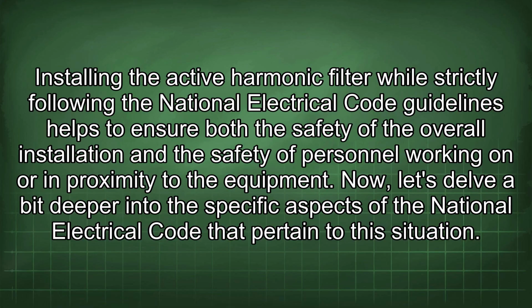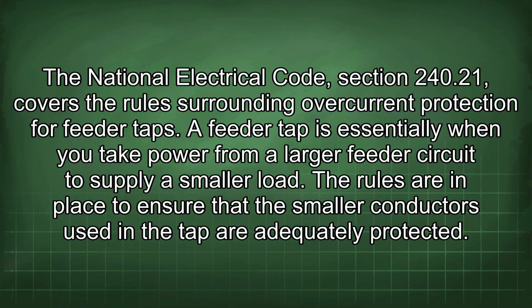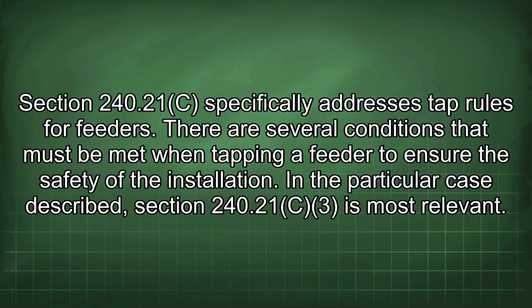Now let's delve a bit deeper into the specific aspects of the National Electrical Code that pertain to this situation. The National Electrical Code, Section 240.21, covers the rules surrounding overcurrent protection for feeder taps. A feeder tap is essentially when you take power from a larger feeder circuit to supply a smaller load. The rules are in place to ensure that the smaller conductors used in the tap are adequately protected. Section 240.21(C) specifically addresses tap rules for feeders. There are several conditions that must be met when tapping a feeder to ensure the safety of the installation.